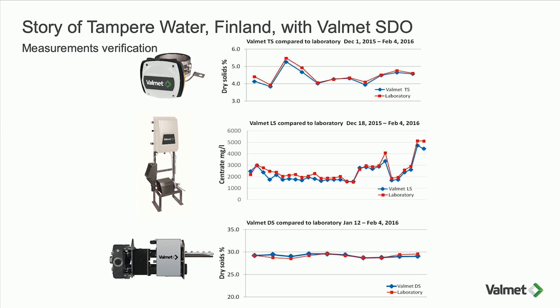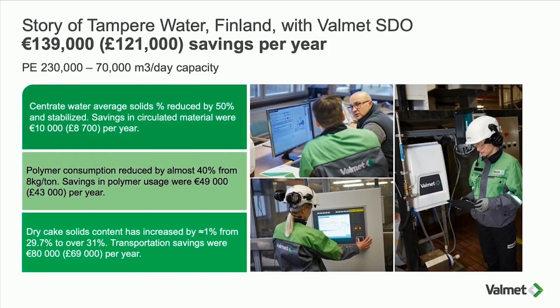Because the measurements performed well, we moved to the next stage: implementing the multi-variable controls. This was a full SDO system — all measurements and controls — and they achieved an annual saving of around £121,000 in the first year. In the second year they increased that figure further as they learned how to run the centrifuge better. Savings came from reduced solids in the centrate going back to the head of works, reduced polymer consumption by around 40%, and the biggest saving came from transport costs where they improved dry cake by about one to one-and-a-half percentage points. Our ROI calculation had actually been quite conservative — they achieved much better savings than anticipated.